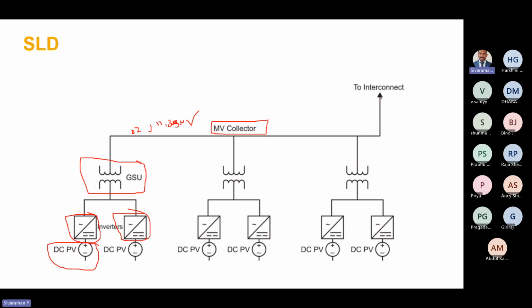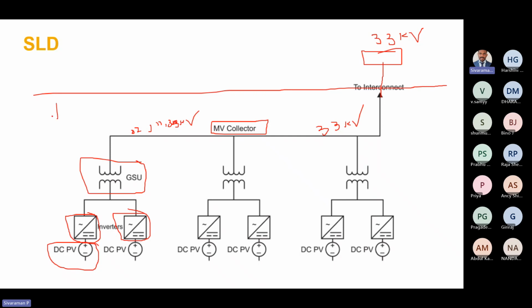So this will be interconnected with the grid. Okay, suppose you have the grid at this location and that grid voltage is 33 kV. Our plant voltage is also 33 kV. So in this case, we do not need a power transformer. We can directly connect our 33 kV plant. This side is the plant, and on the upper side it is the grid. In this case, we do not need a transformer here. We can directly connect this 33 kV voltage level into the existing 33 kV grid.